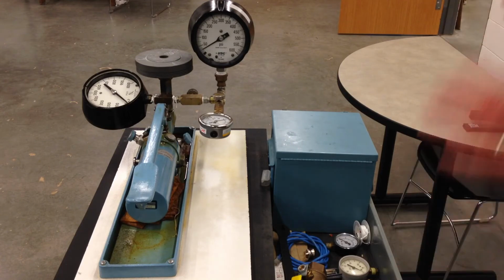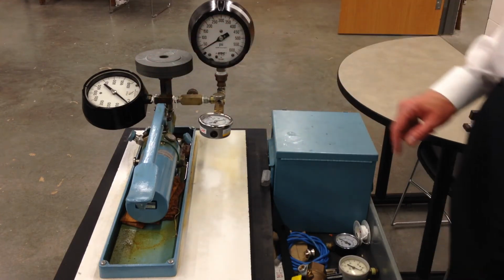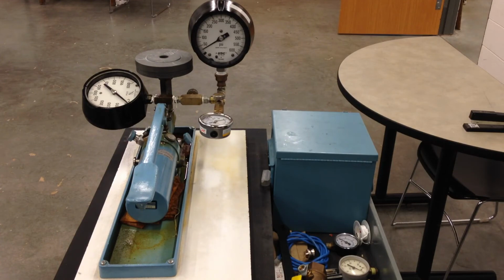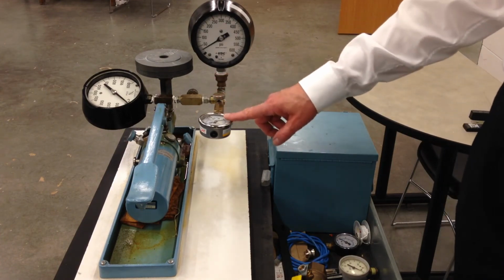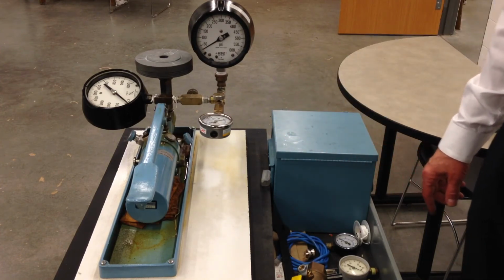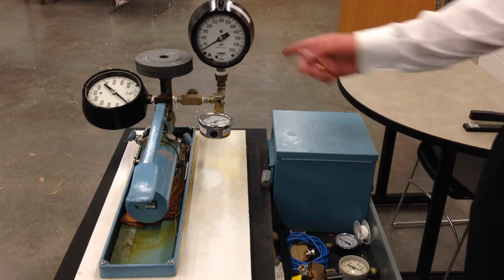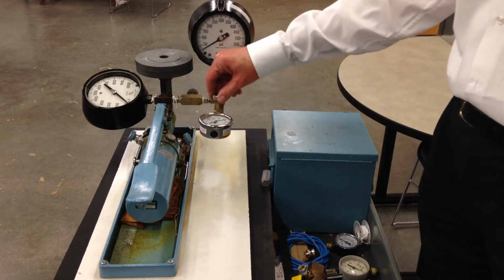Now you ask, 300 psi, 600 psi. What happens when, for example, I get to 350? What's going to happen to this gauge? Well, the worst possible case, of course, is what we call a missile reaction, where the thing would come shooting out. The next worst possible reaction is it starts leaking, and the next after that is the gauge breaks. So what we're going to do to prevent that is we have two needle valves.